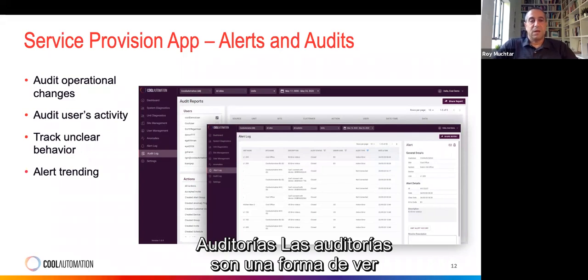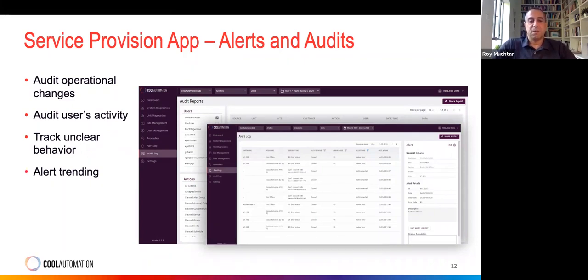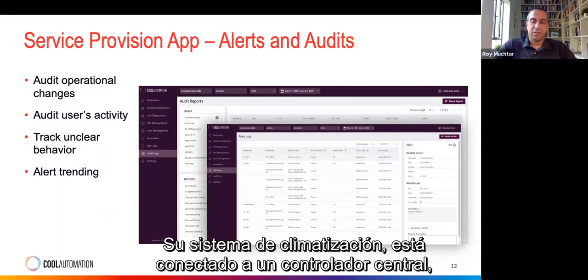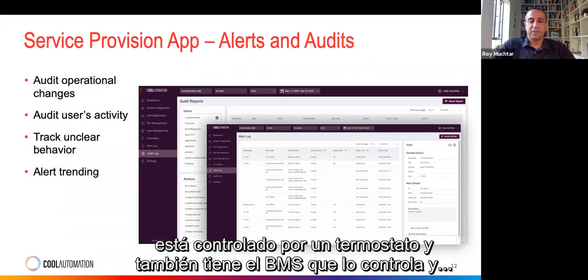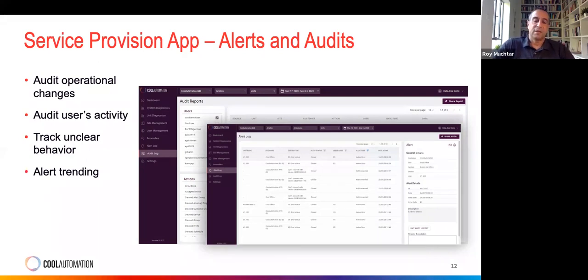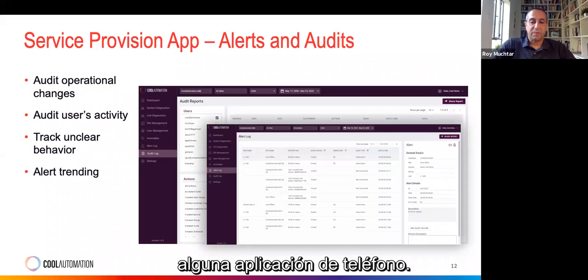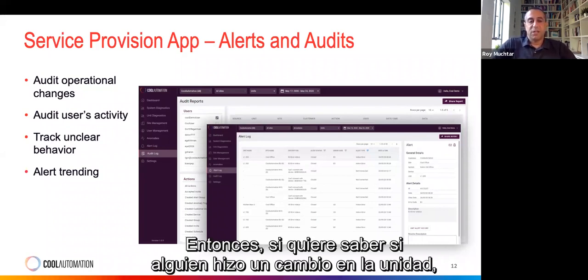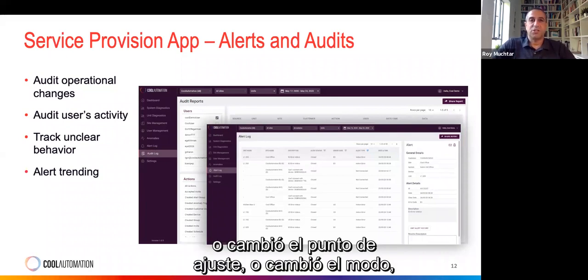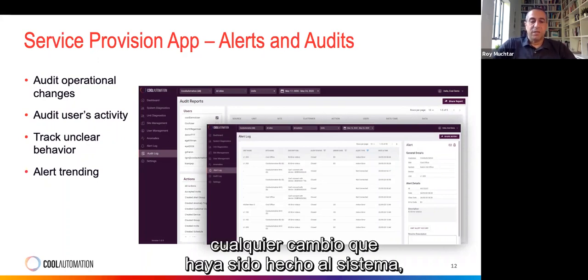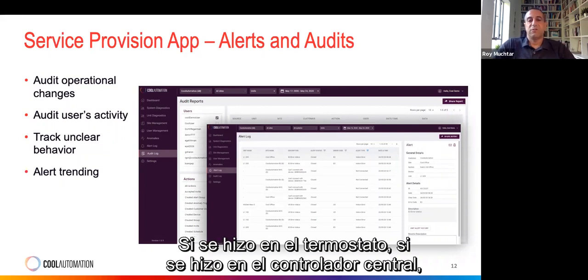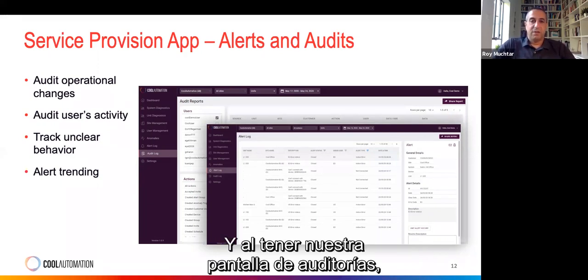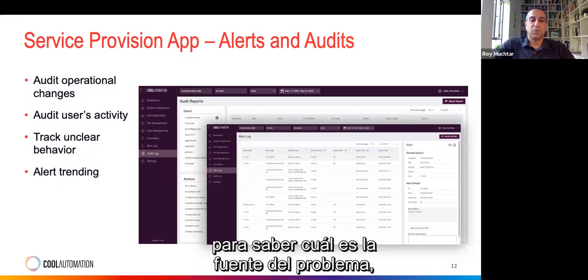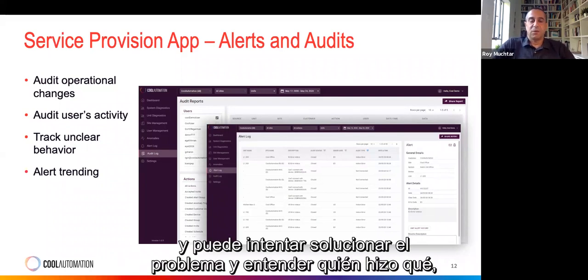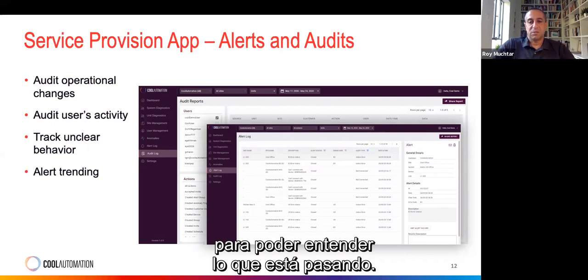Audits. Audits are a way to see who was doing what on the system. Let's say your HVAC system is connected to a central controller, controlled by a thermostat, and also has a BMS controlling it, plus a phone application. You want to know if somebody made a change to the unit, changed the set point, changed the mode, or turned the unit on or off. Any change made to the system, you want to know the source of that change. Whether it was made on the thermostat, the central controller, or through the application. With our audit screen, you can monitor exactly that. You know the source of the issue, when it was done, and you can troubleshoot and understand who did what.